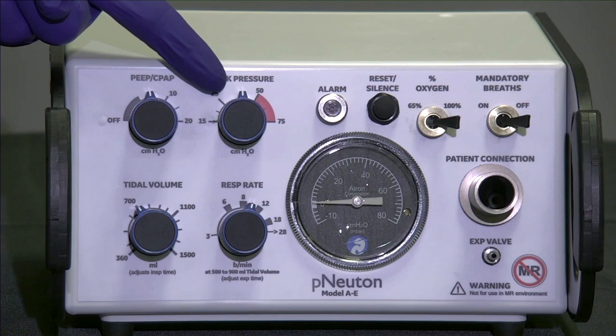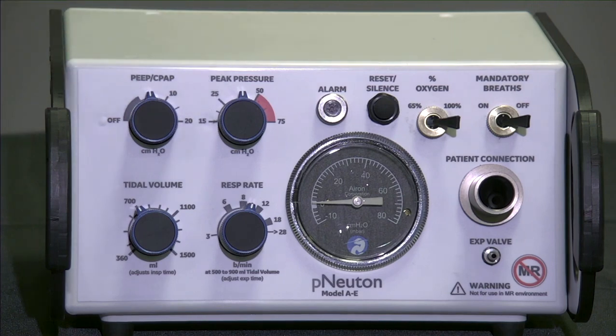Peak pressure control. The peak pressure control should be set above delivered patient pressure. This control limits peak airway pressure to a maximum of 75 centimeters of water pressure. Additionally, this control would be used to set a delivered peak pressure for pressure-limited ventilation.